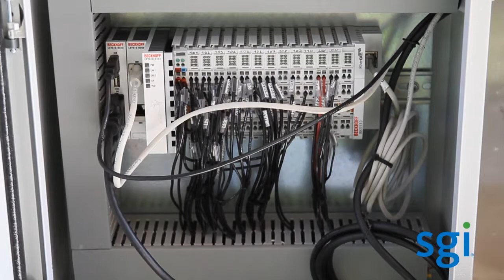For the average person, this is basically a PC. We run a PC as our monitoring control system, and it's modular—you can add various cards as needed to connect various sensors. There are a ton of sensors in this unit: air temperature sensors, water leak detection sensors, and sniffing sensors for the fire suppression or VESDA system. This PC connects through a Cat5 RJ45, Cat5/Cat6 cable.